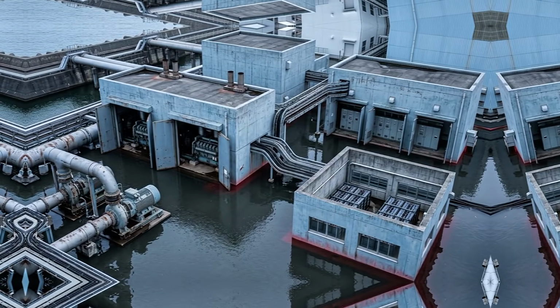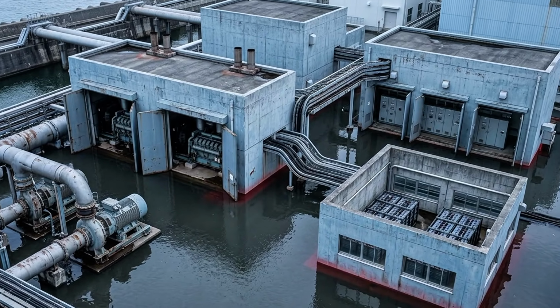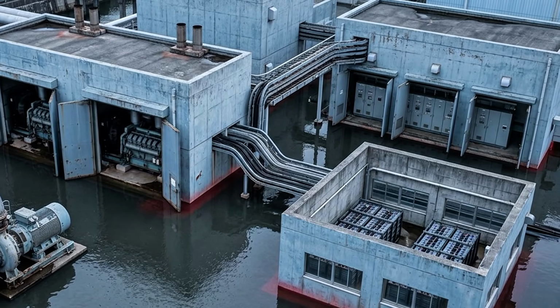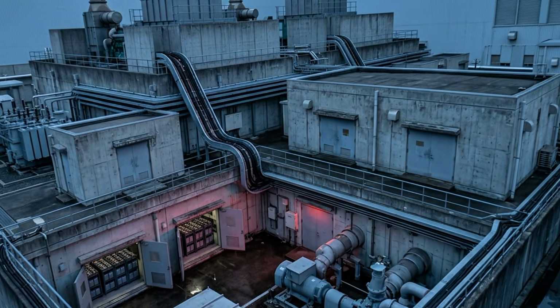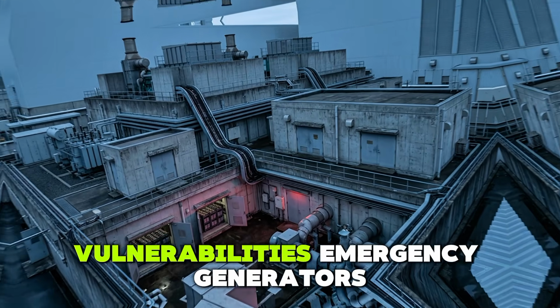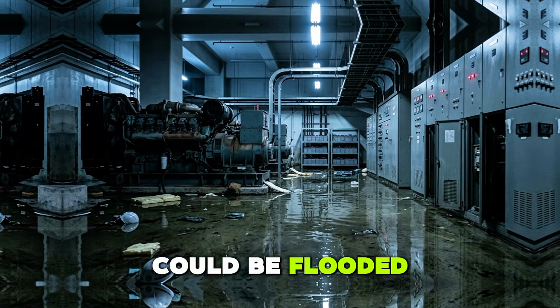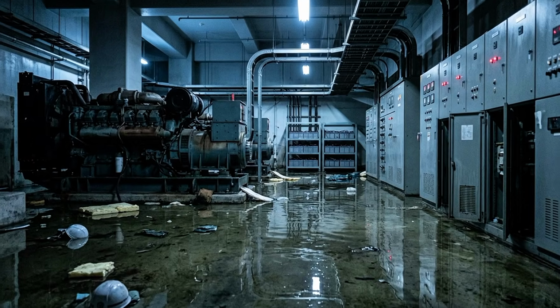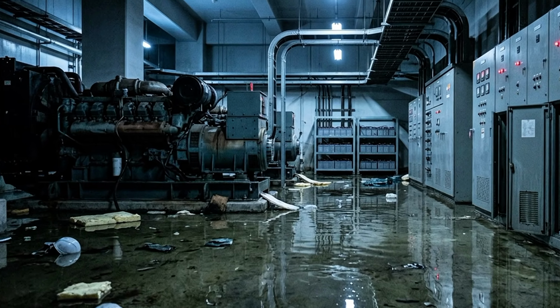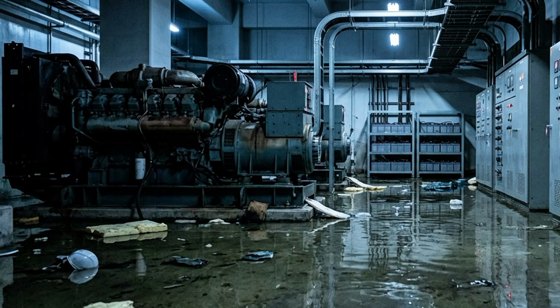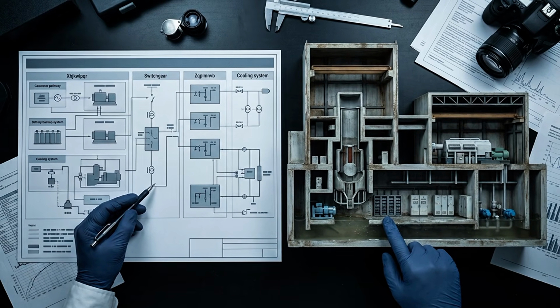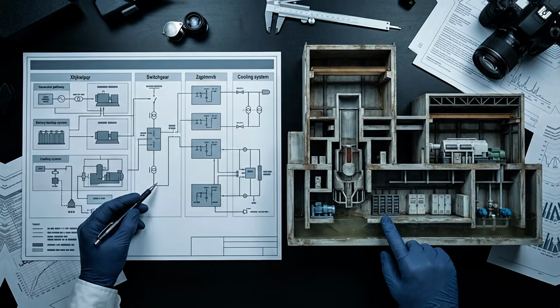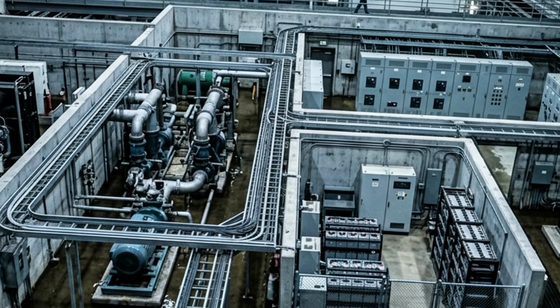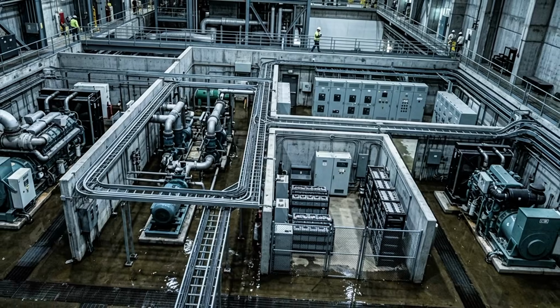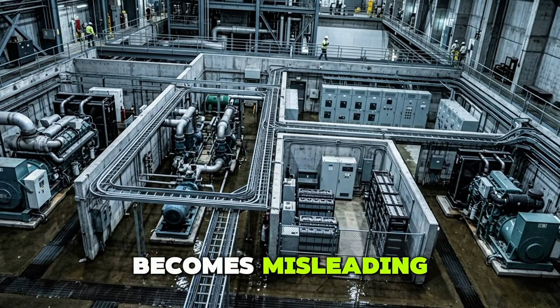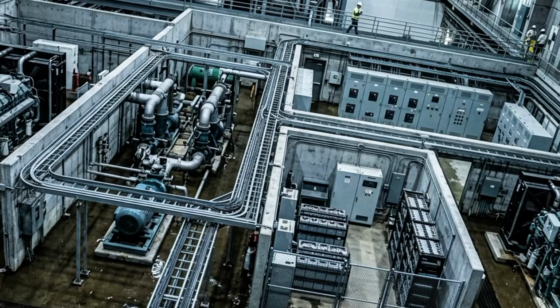Why could one external event disable so many functions required to keep the reactors safe? The answer was not that Fukushima had no backups. It had many. The deeper problem was that critical systems shared vulnerabilities. Emergency generators could be flooded. Switchgear could be flooded. Batteries could be flooded. Electrical distribution could be damaged. Heat removal infrastructure could be lost. The systems could appear separate on a diagram while remaining vulnerable to the same physical event. That is common mode failure. If 5 emergency systems depend on equipment in the same flood-prone area, the number 5 becomes misleading. They are separate systems. They are not truly independent.